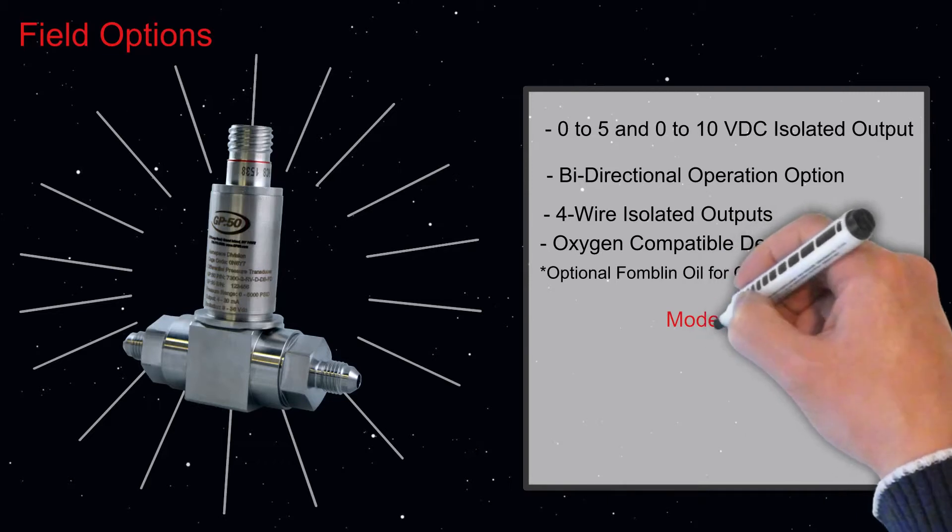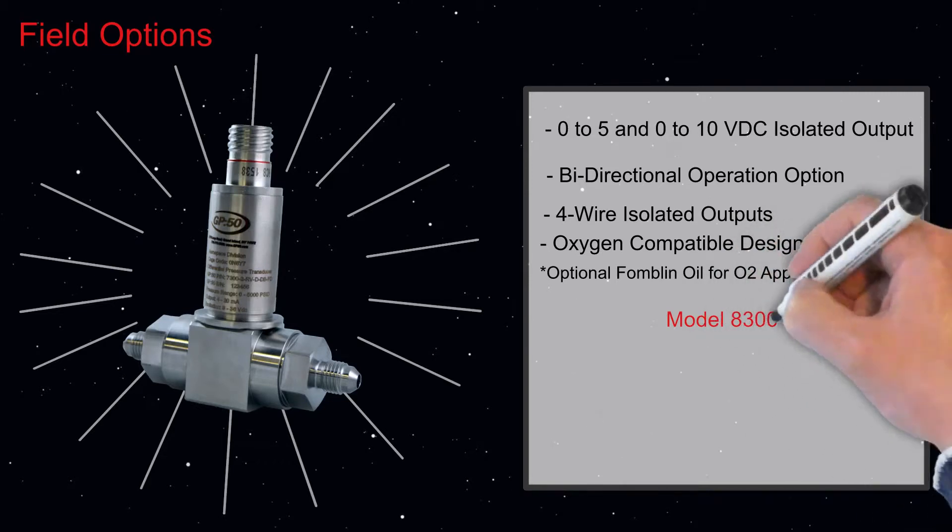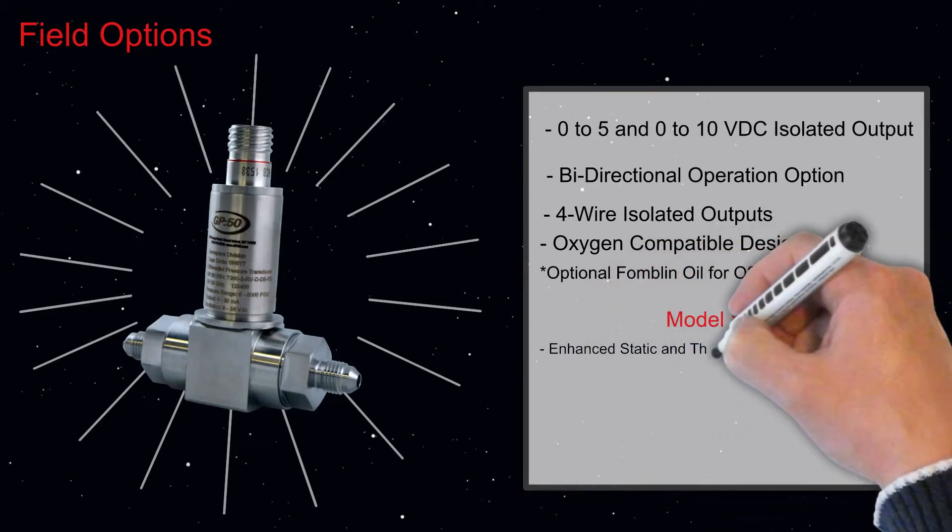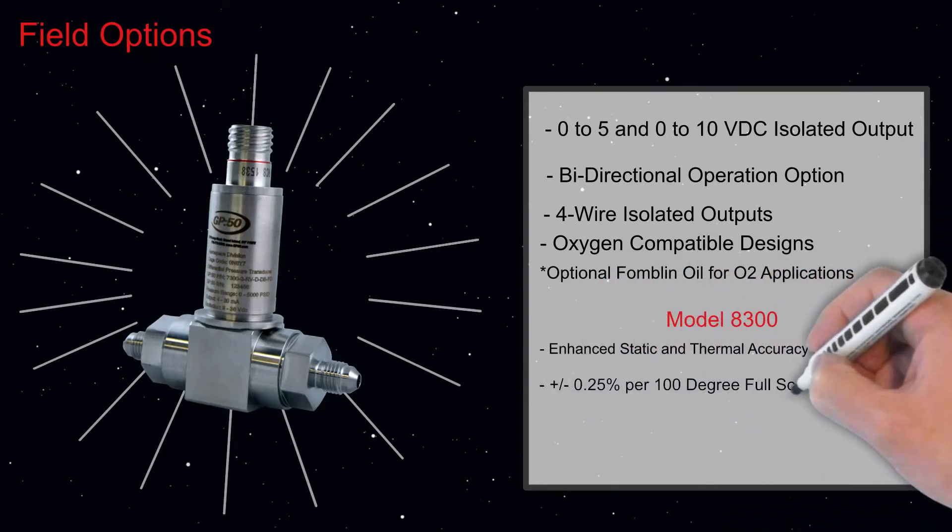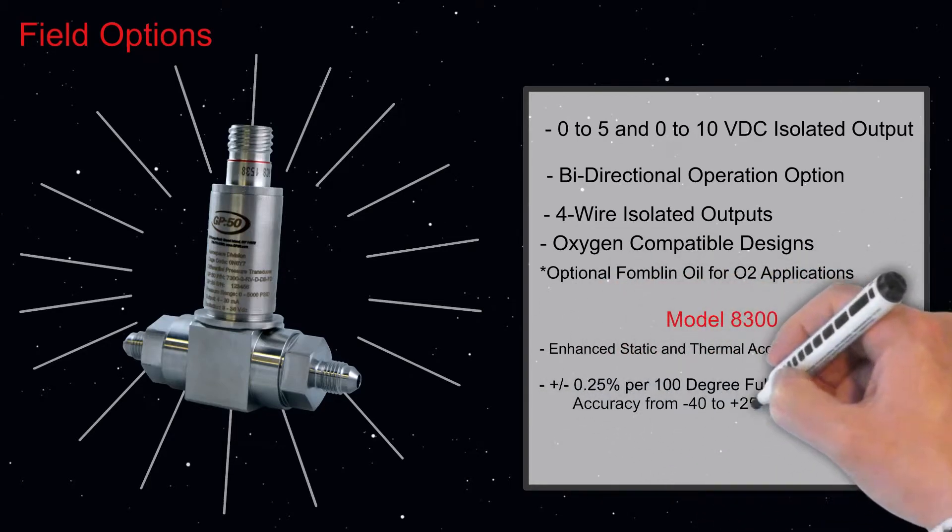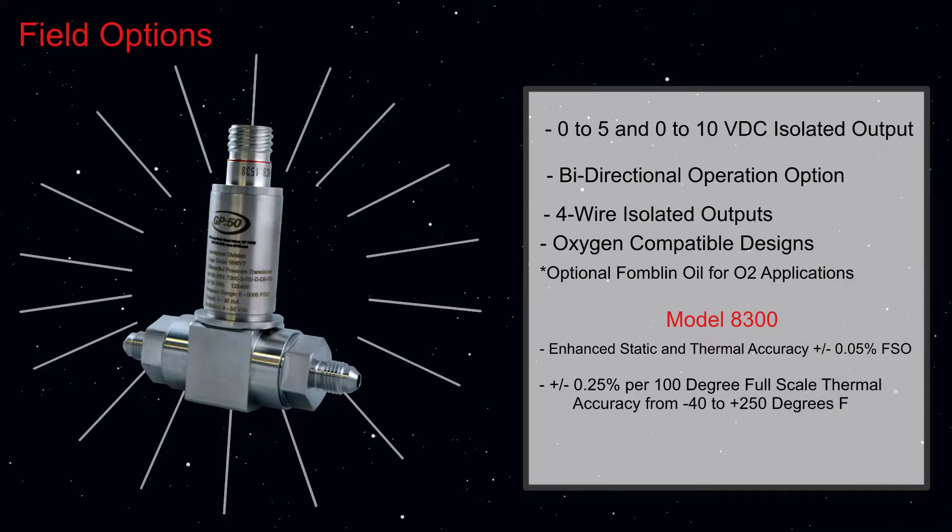The 8300 series offers improved static and thermal accuracy to plus or minus 0.05% full-scale output, with a plus or minus 0.25% per 100 degrees Fahrenheit full-scale thermal accuracy from minus 40 to plus 250 degrees Fahrenheit.